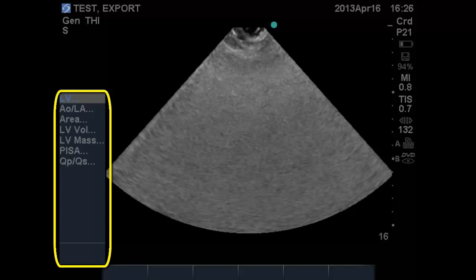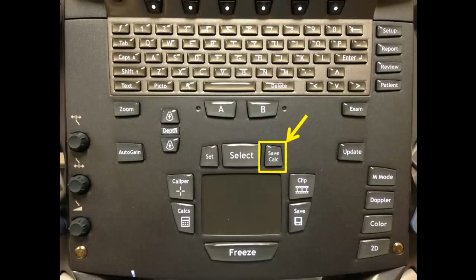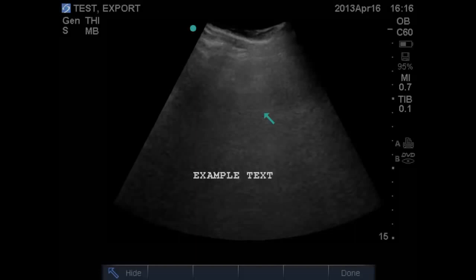The Calcs key will toggle a menu of probe and preset-specific measurements that can be completed for the image on the screen. These measurements are acquired in a similar fashion to those with the generic caliper tool, but in this case use the Set key to confirm final placement, and the Save Calc key may be used to export measurements to the patient record. The Text key will toggle an on-screen keyboard to allow additional labeling. In addition, the arrow key will activate an on-screen arrow that can be moved into position using the trackpad. All images captured with text, arrows, or measurements on the screen will be saved with this additional information included.